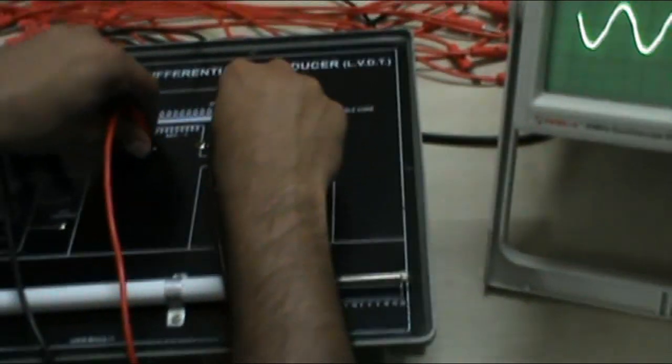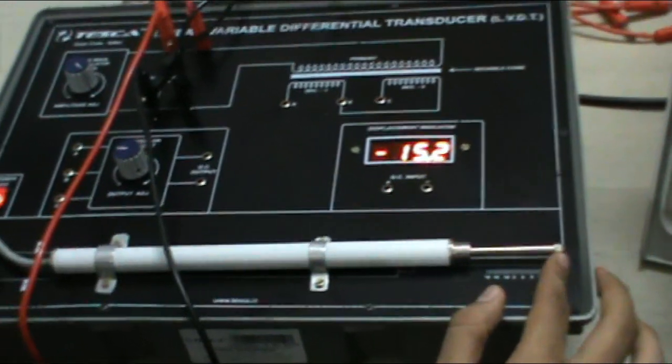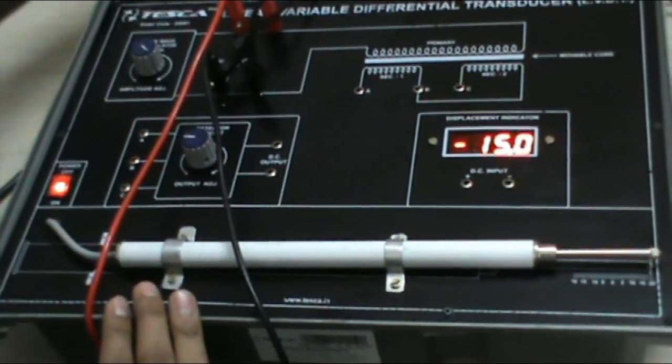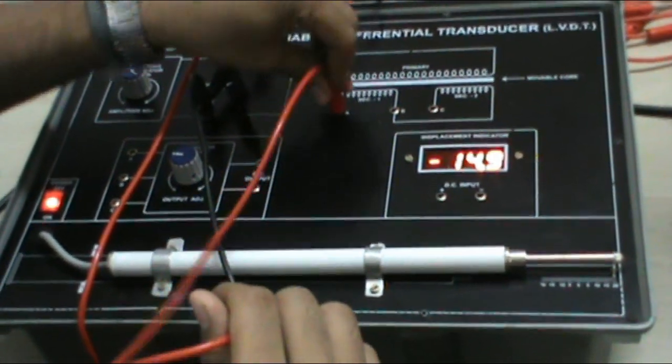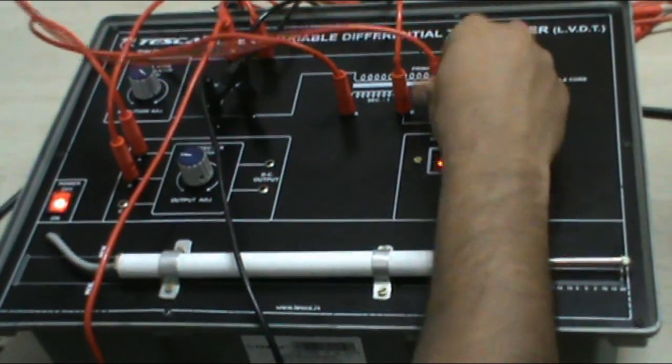Now in order to see the displacement function and how it works, first of all connect this LVDT output to the detector circuit. A to A, B to B, and C to C.